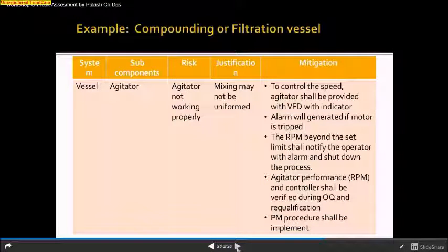The agitator shall be provided with a VFD with indicator, that is a variable frequency drive. An alarm should be generated if the motor is tripped, and if the RPM goes beyond the set limit it shall notify the operator with the alarm and shut down the process. So these are the controls. Then agitator performance shall be controlled and verified during the OQ, and the same shall be reviewed in the requalifications. A PM procedure shall be in place. In between, it should be covered by the PM whether the agitator is working or not.